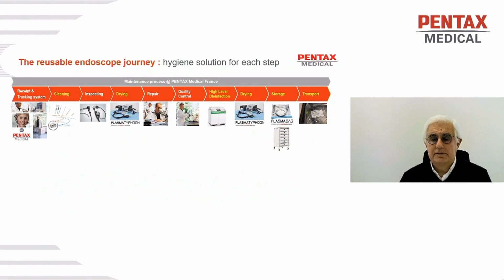It's really the same best result, whatever the scope is and whatever it is in the morning, whether my tech is sick or tired, it's reproducible. Then we move to the storage. The endoscope is put in the plasma bag, with the injection of ozone, which means that the environment around the endoscope is bacteriologically static. Even if the bag or the endoscope, which is unlikely, has some residual contamination, it doesn't develop; it stays as it was getting in.